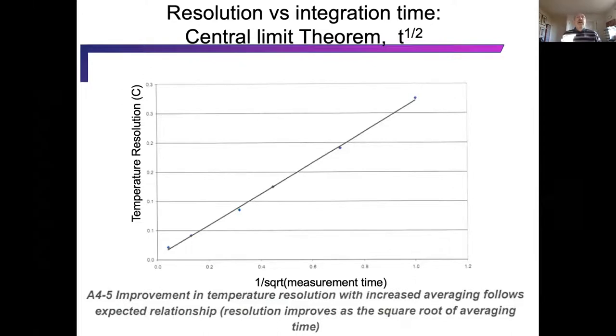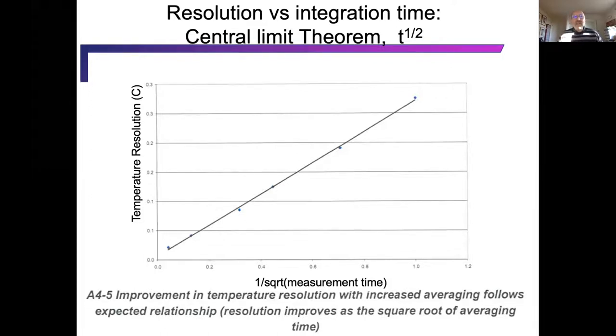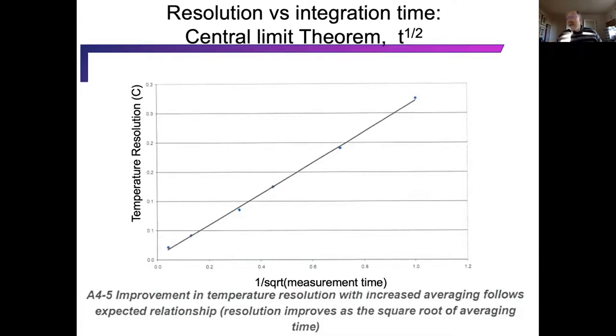With respect to temperature resolution, we are really counting photons. When we hold our instrument open for a minute of collection, we get a rate of photon collection. The uncertainty of the mean rate of photon collection goes with the square root of time — from standard large-number statistical concepts. Temperature resolution as a function of one over the square root of measurement time is very linear, confirming the central limit theorem works. A one-second measurement will be roughly 10 times less accurate than a 100-second measurement.